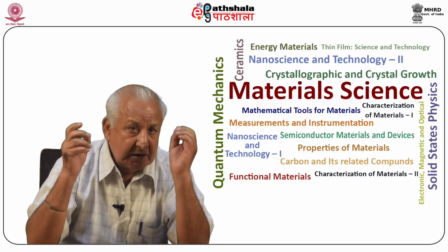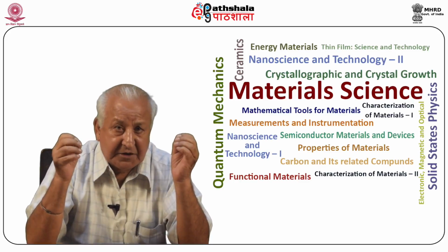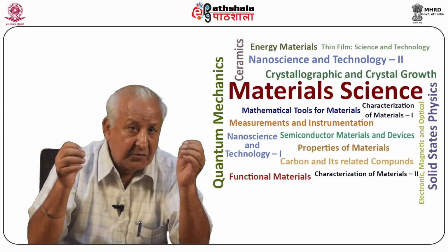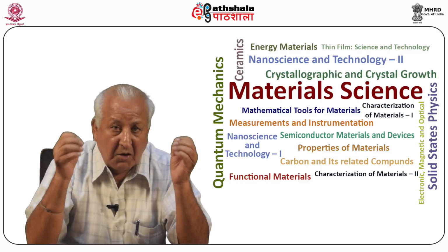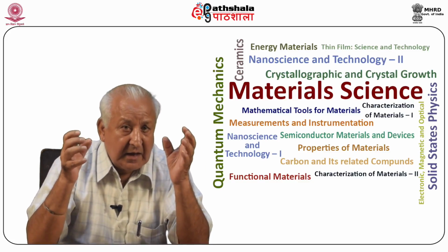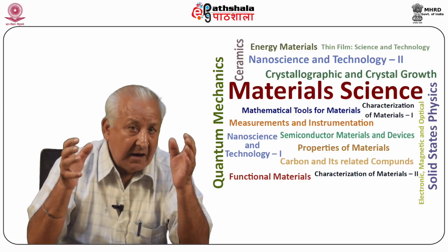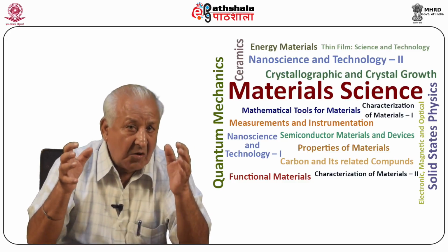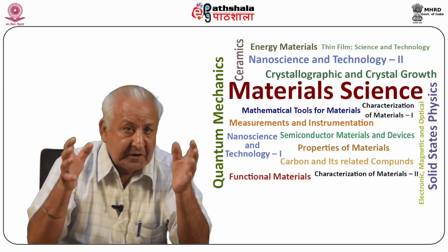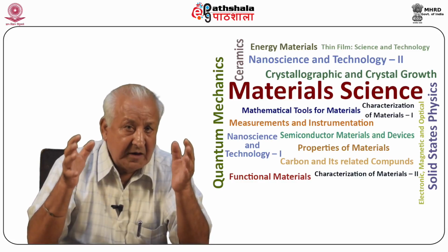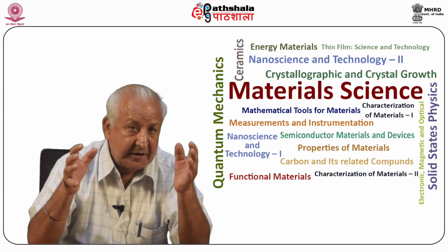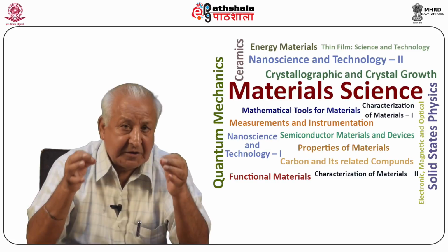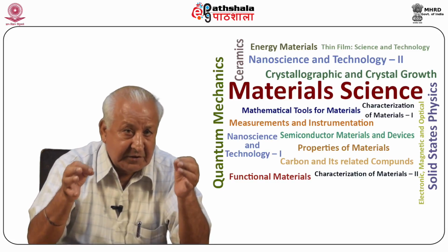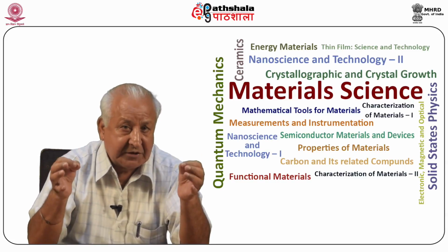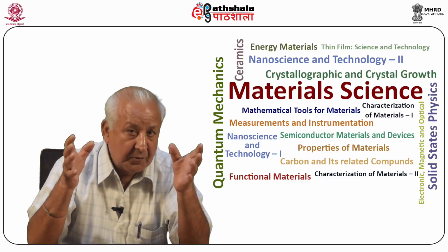To improve resolution, it is required to increase the value of mu and alpha and have lambda as small as possible. In optical microscopes, oil immersion objectives are provided, in which a drop of special oil is used between the specimen and the objective to increase mu.